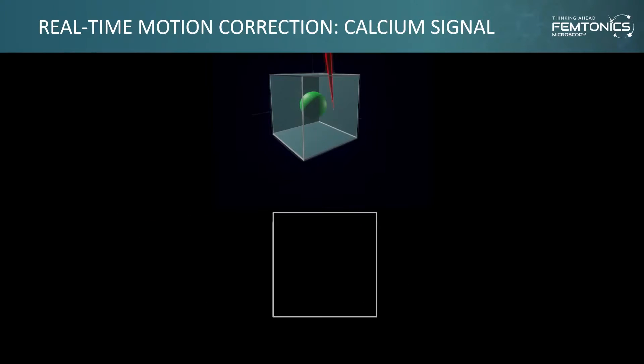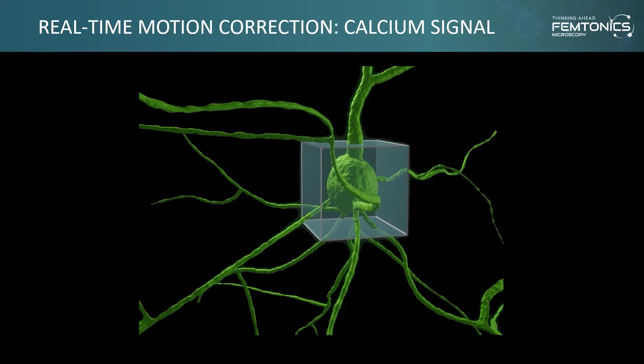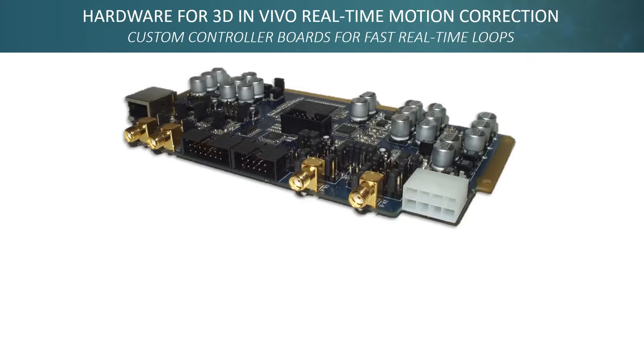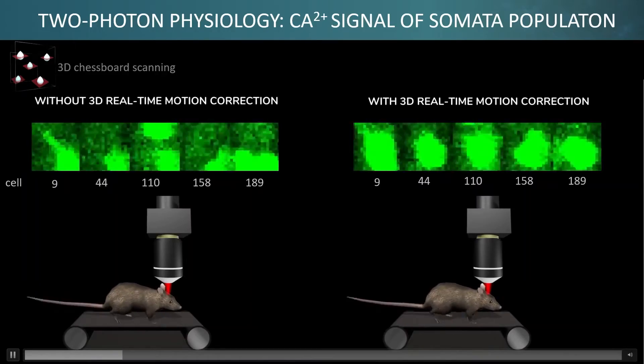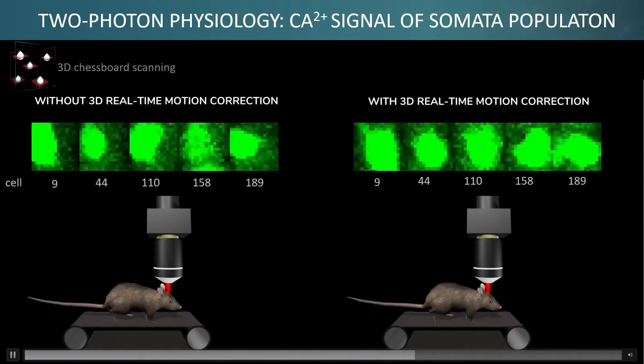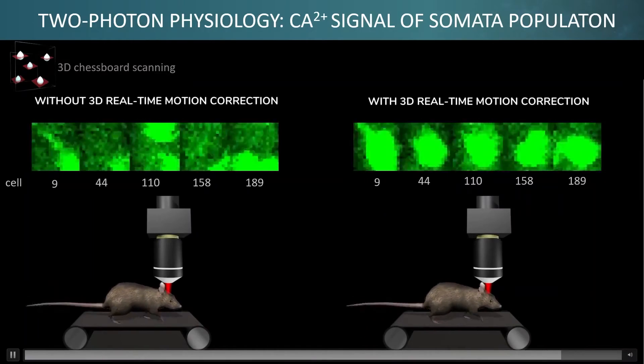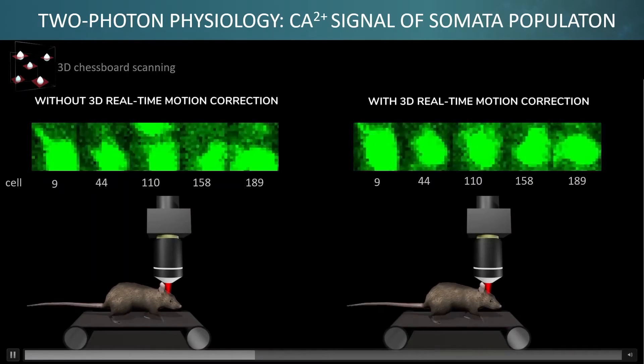Then, at the FPGA level, the firmware calculates the dislocation vectors between the centroids of the intensity profiles of subsequent reference drifts in each direction — X, Y, and Z. Based on this estimation, the movement will be compensated on the next imaging drifts by shifting the target of the focal point. Since a very fast, less than one millisecond intervention is needed, calculations are performed not on the personal computer level, but on the electronic cards controlling the photomultiplier and acousto-optic crystals. Using this approach, Femtonics Focus Spinner can compensate the motion of the cell population quite robustly. Moreover, keeping the neuron in the ROI does not require increasing the size of the scanned ROI, which would mean a significant reduction in sampling rate. The frame rate decreases only by the user-predefined fraction between reference and imaging drifts.